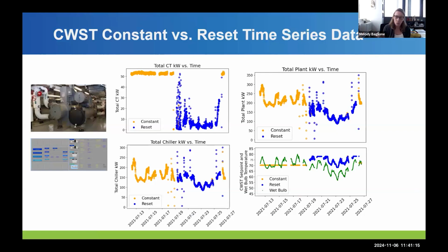Here's just showing 2 weeks, 1 week where the system was in a constant mode. You can see that here in yellow, the constant condenser water supply temperature set points. And then you can see the reset condenser water supply temperature set points in blue. And then you see the chiller and the cooling tower and the total plant kilowatts.